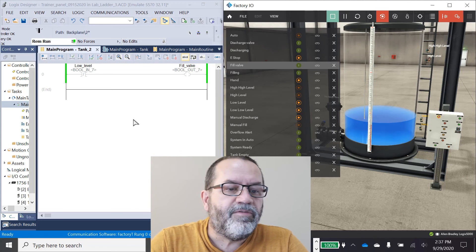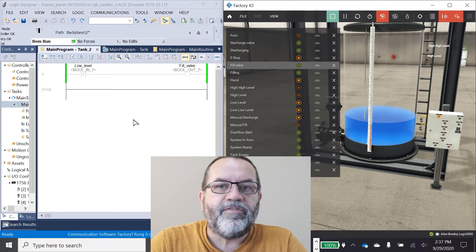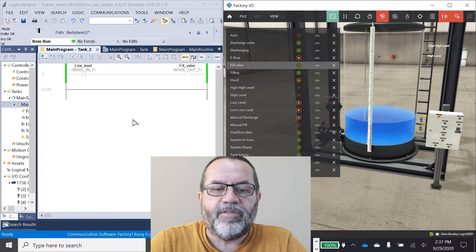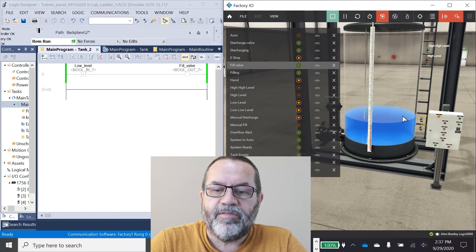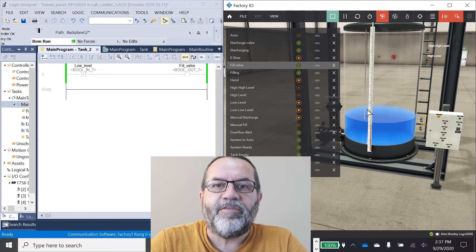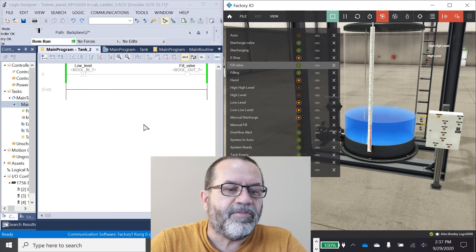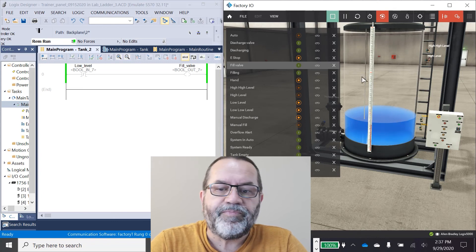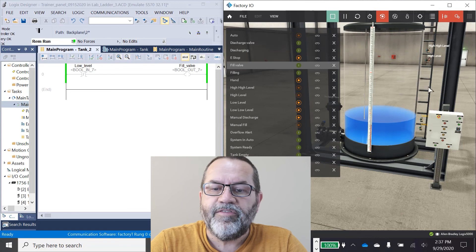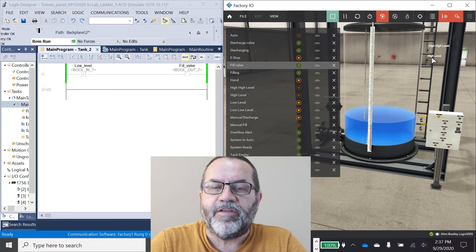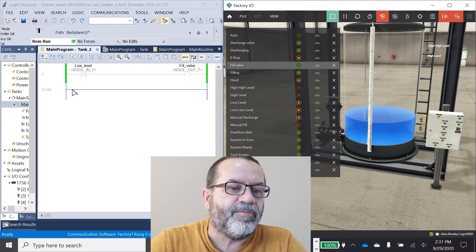I'm going to put in a seal-in so that when the fill valve opens, it can keep itself open and stay open until I hit the high level.